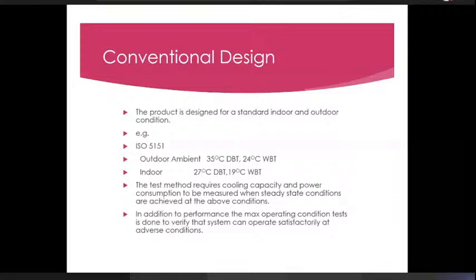So this is the condition, and if some of you are not familiar with these conditions, you might think 27 is too high. Essentially, it's a return air temperature. So if we are sitting in a room which is at 25, there will be a temperature rise between the temperature we are experiencing and the temperature that goes to the heat exchanger. So some part of it is that, and some part of it is standardization with other standards internationally. It is a number that matches the standards used in Europe, US, and Australia. So to that extent, there is harmonization of the standard also.